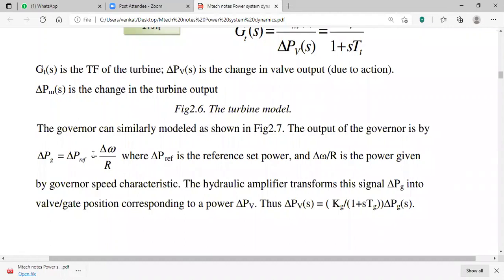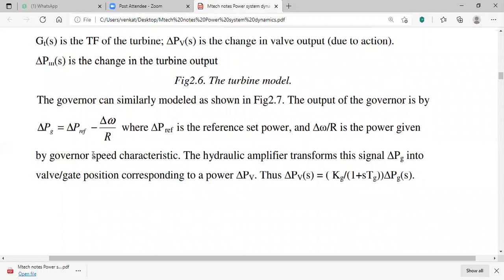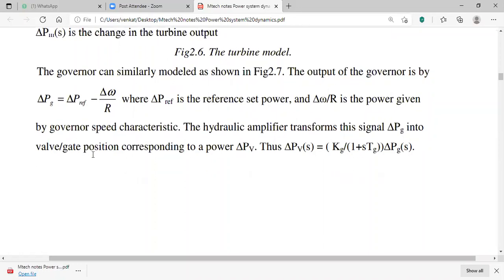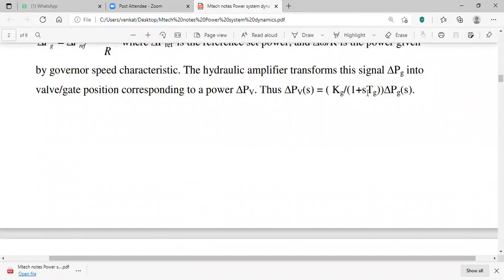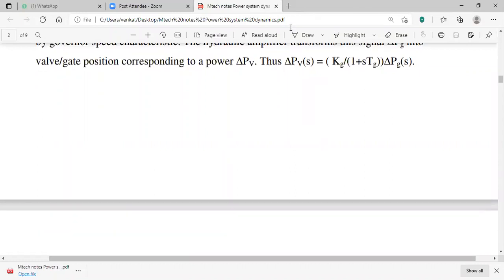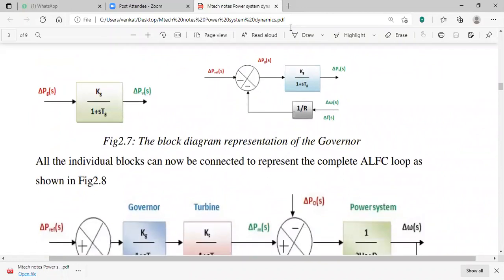The governor can similarly be modeled, as shown in Figure 2.7. The output of the governor is: delta PG = delta P-reference minus (delta-omega / R), where delta P-reference is the reference set power and delta-omega / R is the power given by the governor's speed characteristics. The hydraulic amplifier transforms this signal into valve position corresponding to delta PV, written as: delta PV = [KG / (1 + s·TG)] × delta PG.